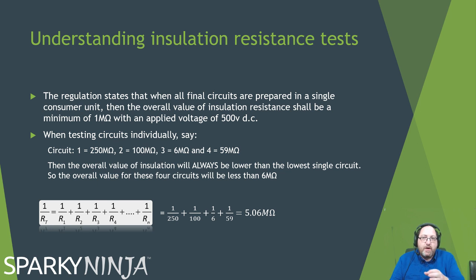Right? So if one of these single circuits measured 2, I know my overall value will be below 2. That is important to remember, because in the assessment they might give you the rules, and the answer is lower than the lowest. Or it might give you 4 measurements of insulation resistance and want you to do the math. Remember, if it's a multiple choice assessment, just select the answer that's lower than any of the given measurements. Okay, the overall value in parallel will always be lower than the lowest single measured value.